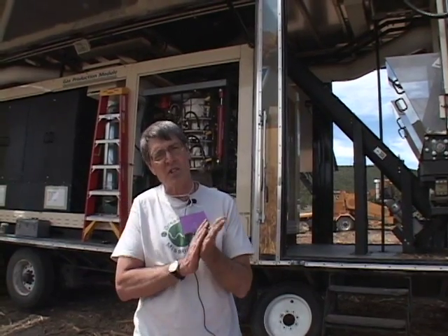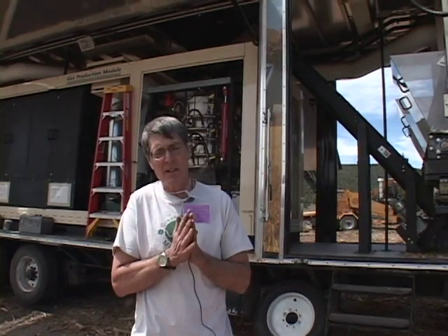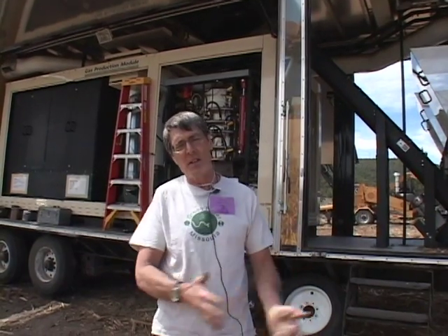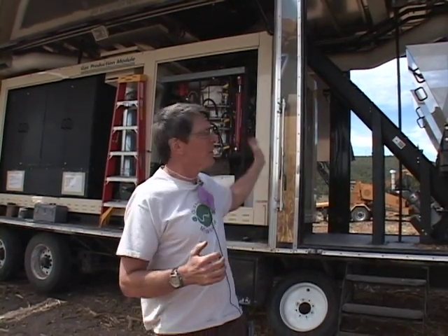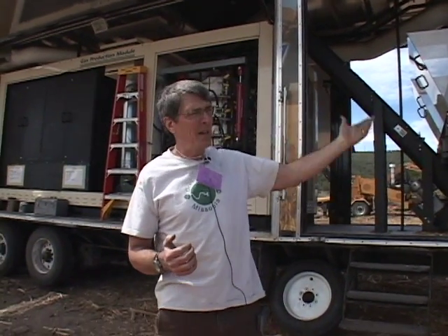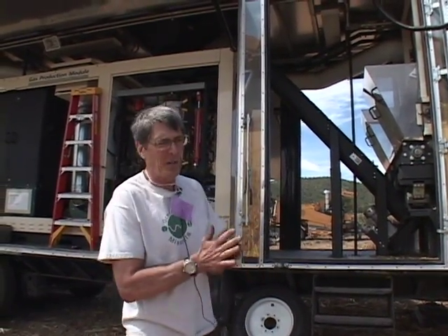We've used some pretty ugly slash in it. We've had clay, rocks, metals, all sorts of things go through it. So it does a fairly good job of handling it, but still, if we were to switch our feedstocks to, say, pellets or cherry pits, as one of your colleagues recommended, the clearances in the auger systems are too great, I think, to conduct that material efficiently through the system. So most of my headaches are in the front part of the system with handling, drying, conveying wood chips into the reactor.